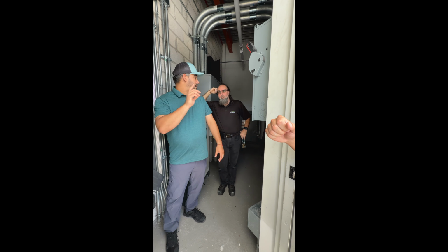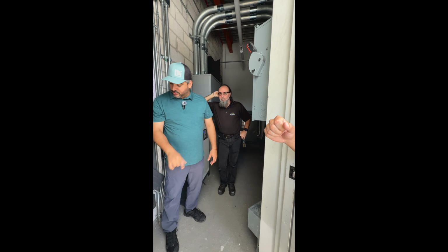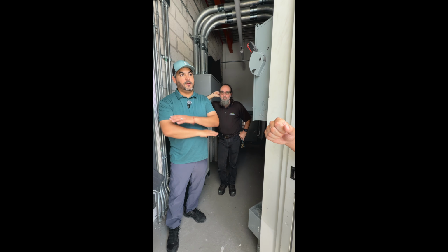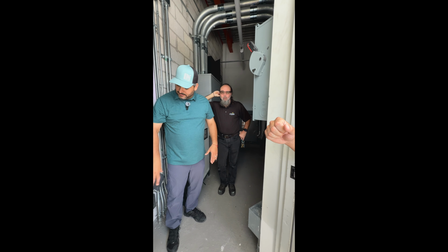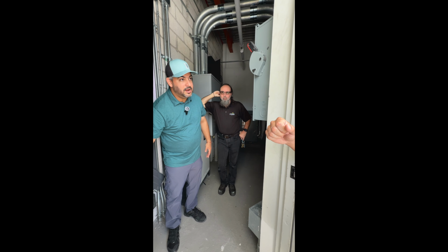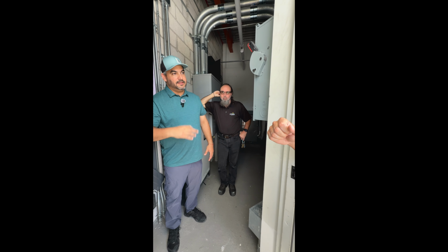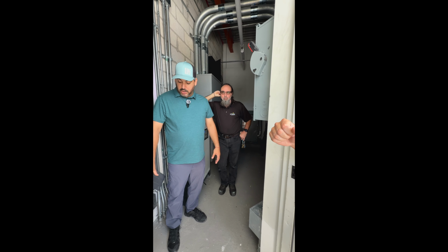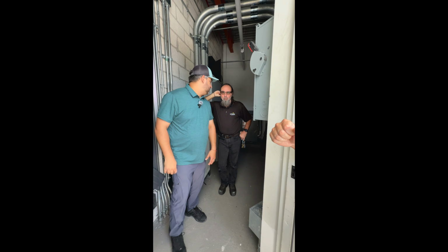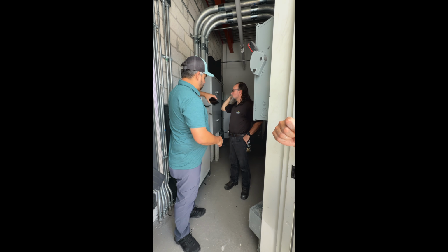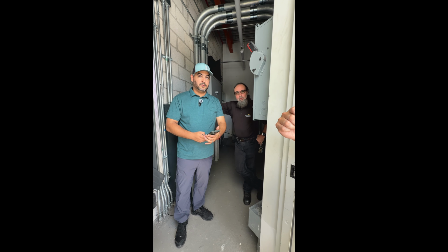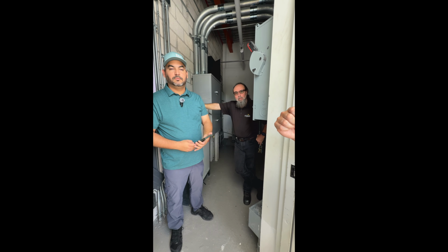No, because if a surge will affect the panel, the first thing you will notice is that the time clock and the date are going to be completely off. And this device back here has a battery that will hold the programming. Even if you disconnect the power from the panel, it will hold the programming. Let me see if I can take a picture. So as it stands now, all the lights come on at sunset and go off at sunrise. Astronomical. Yes. Okay.